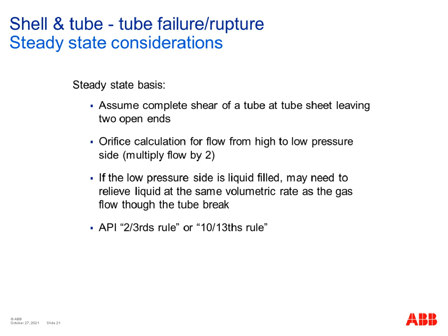Tube rupture may also be eliminated as a possibility based on an assessment of the failure mechanisms and a determination of whether this is actually credible or not. This will be covered a bit later in the presentation. However, it's always difficult to be completely sure a possibility is not credible, that it's eliminated. A more general point: protecting heat exchangers from overpressure is fundamentally the same as with any other item of equipment. However, they do present the following specific problems. The type and extent of internal failure that can be anticipated is one. Selection of a relieving device that reacts fast enough to prevent the overpressure is another. And selection of the proper location for the device so that it senses the overpressure in time to react to it. And we're particularly going to discuss this in the next few slides.